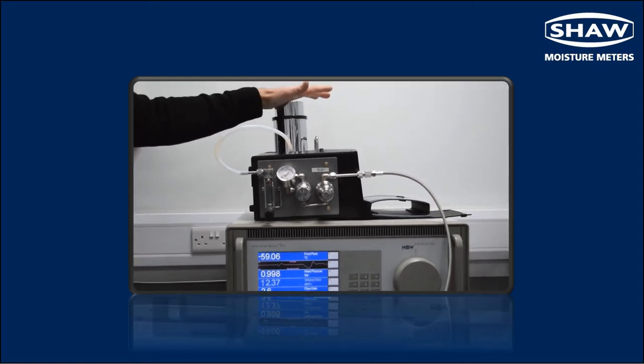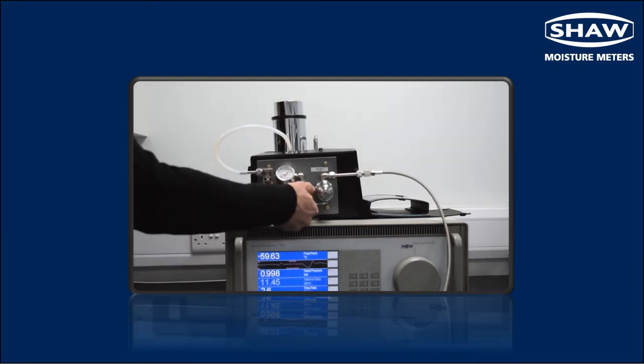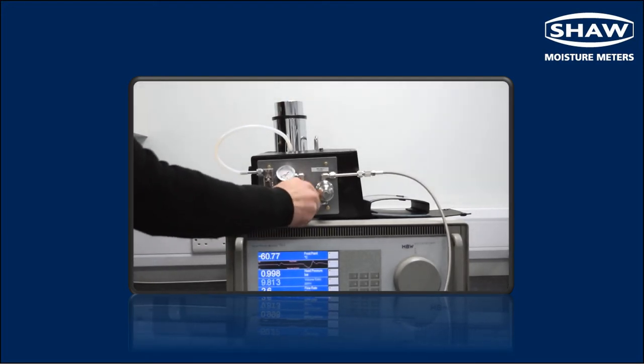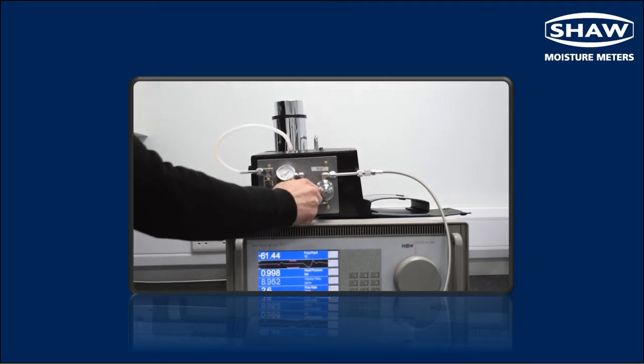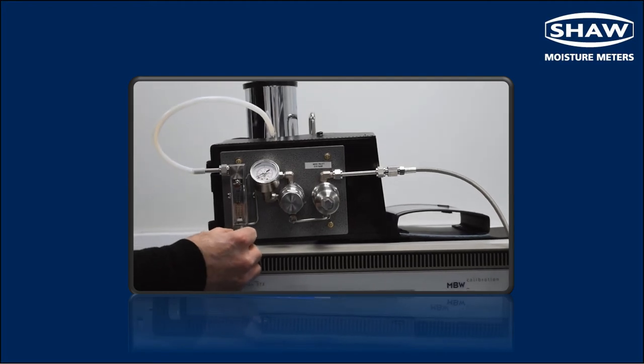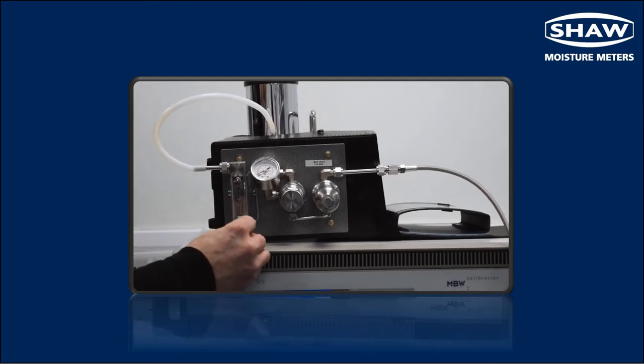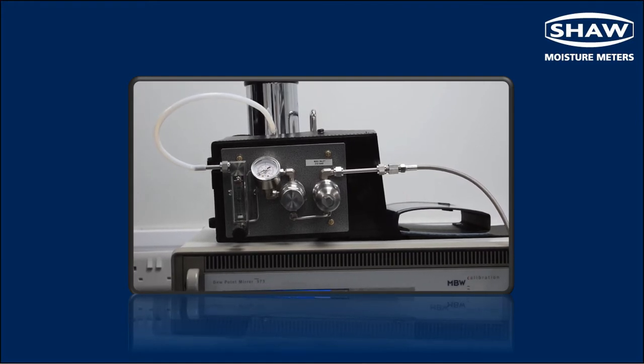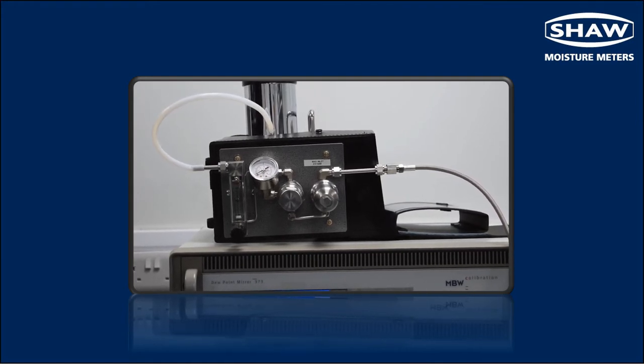So first of all, open the pressure regulator. Then we can adjust the flow meter. So for sampling we want a flow of about 2 to 5 litres, but for purging we can go higher than that.